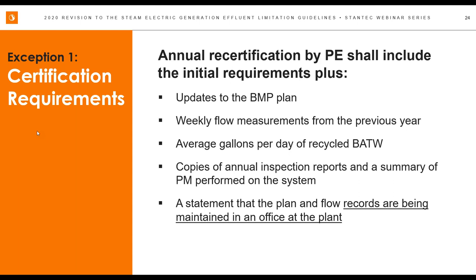And this is one that I emphasized once again, based on my familiarity with how stations operate and how many utilities are trying to go to more centralized programs: a statement that the plan and flow records are being maintained in an office at the plant. Having it down at your central engineering offices, or in your regional SME's office who's supporting this equipment, is not at the plant as the rule is currently written. So be aware of that.